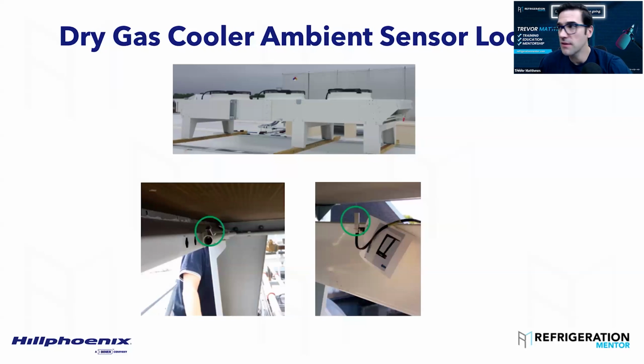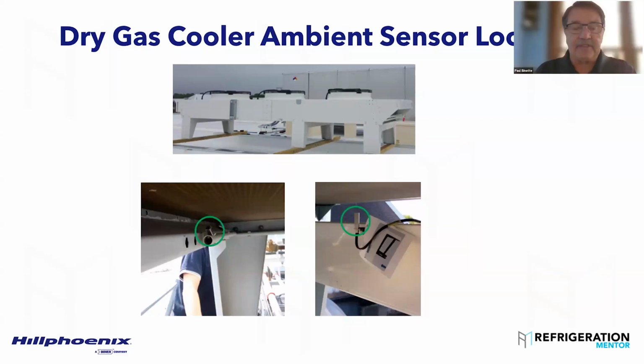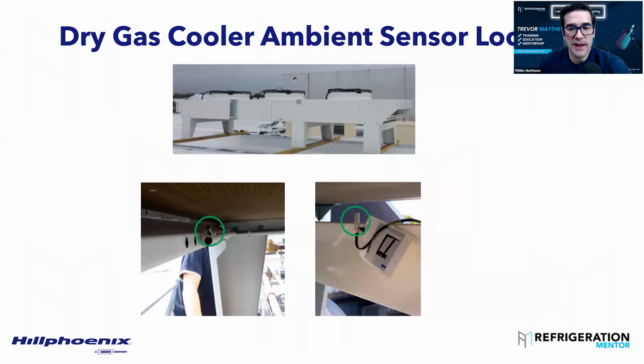Yep. Now I'll maybe be able to pull one up in a little bit. Let me look through it. What was that question? When we use adiabatic pre-cooling pads in the gas cooler, should we tell the controller the actual ambient temperature or the temperature of the air after the pads?